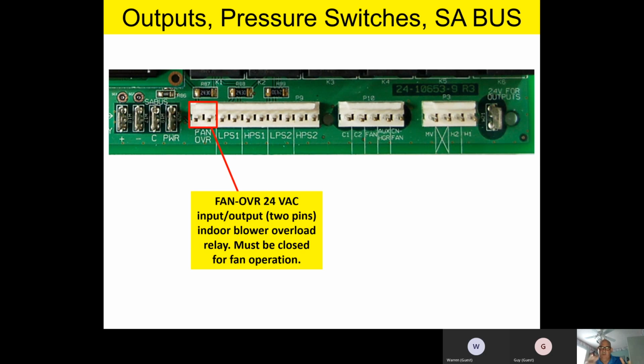It's really important if he uses a rescue motor or a non-OEM motor as a replacement to get the unit going. I'm perfectly fine with that as long as the rotation and the RPM and everything is right on it. But just please remember, he's going to have to go down to this fan overload input, and he's going to cut his wires back several inches so he can effect a repair later on. He's going to have to wire nut those harness wires together so that fan will run, because if that circuit is open electrically, you will not have a fan output on those previous pins we were talking about, and the indoor blower will not run. Any questions or comments on that?